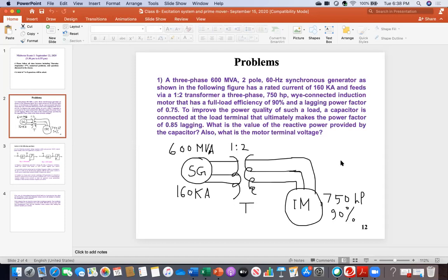First, you should get the VL line voltage of 2.17 kV. That is for the generator, at the terminal of the generator, here on the primary side of the transformer. Then you see the turn ratio: the secondary side has 2 times more turns, so you just need to multiply by 2. And we did not put any line or any resistance or reactance, so there is no drop. The secondary of the transformer appears directly as the motor terminal. So it should be 4.33 kV.